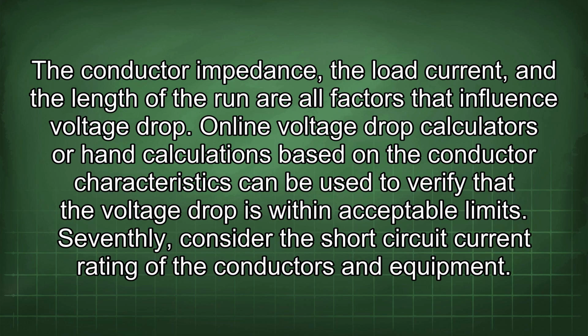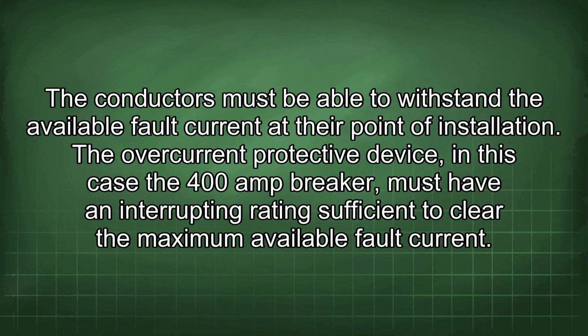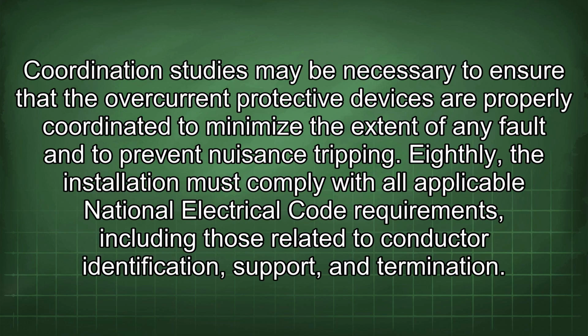is within acceptable limits. Seventhly, consider the short circuit current rating of the conductors and equipment. The conductors must be able to withstand the available fault current at their point of installation. The overcurrent protective device, in this case the 400 amp breaker, must have an interrupting rating sufficient to clear the maximum available fault current. Coordination studies may be necessary to ensure that the overcurrent protective devices are properly coordinated to minimize the extent of any fault and to prevent nuisance tripping.